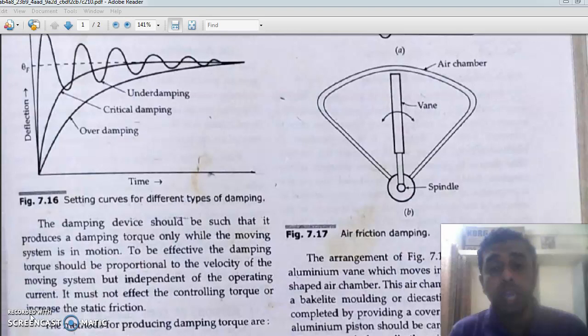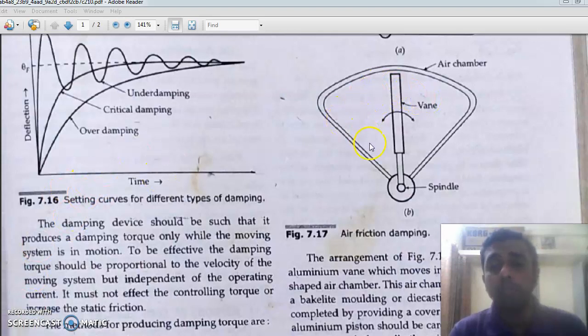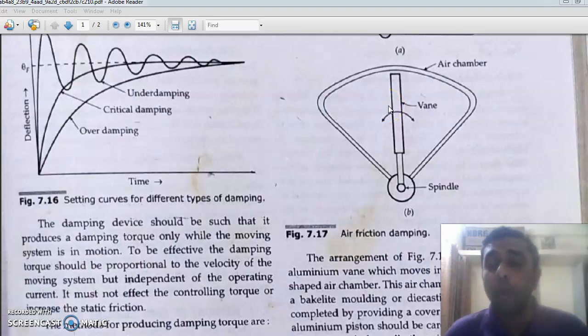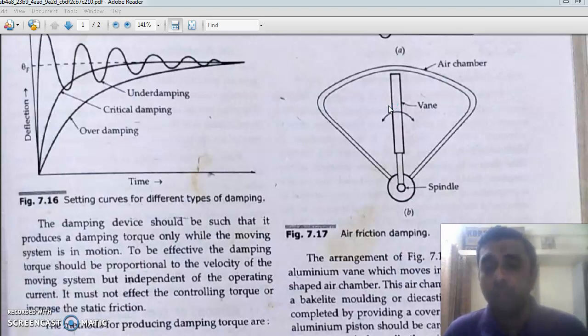That type used a piston and chamber arrangement for causing air friction damping. Another type is a chamber type where the instrument itself — the screen or the chamber of the instrument — will be an air chamber. So the pointer will be moving inside the pressurized air chamber, and the pressurized air will give opposition to that vane or the pointer, providing a force of opposition that will nullify the swings.